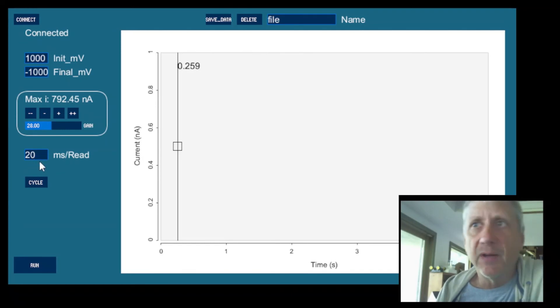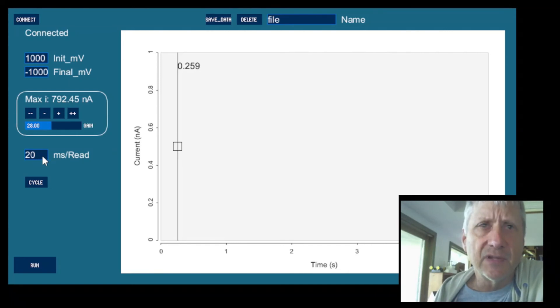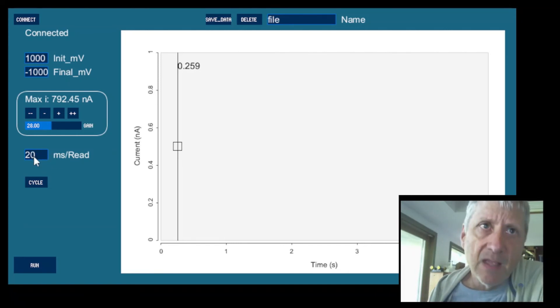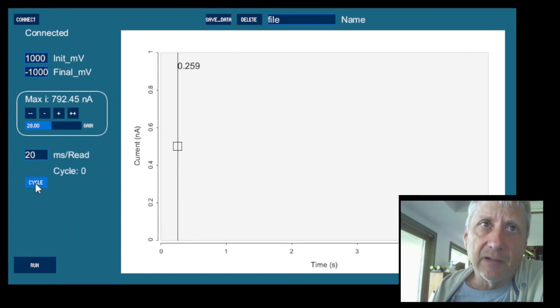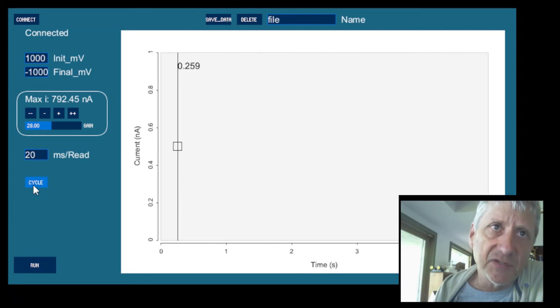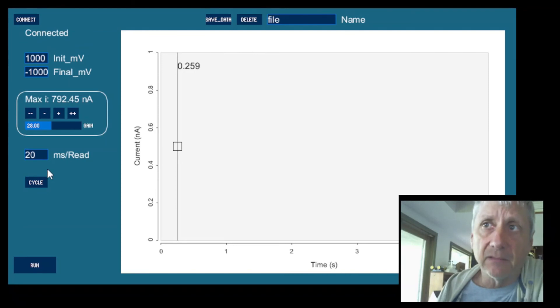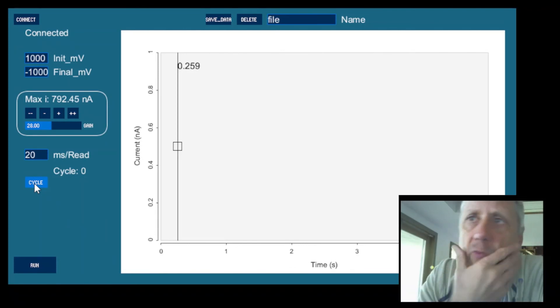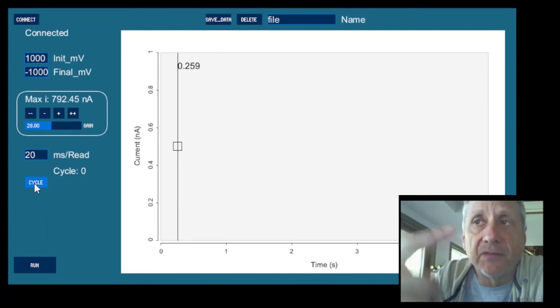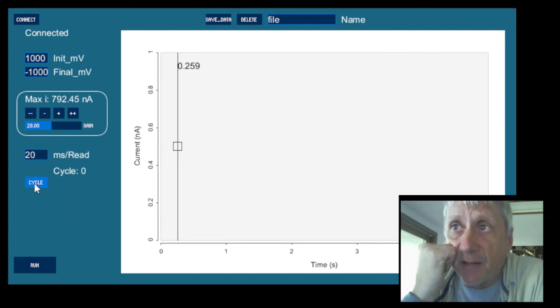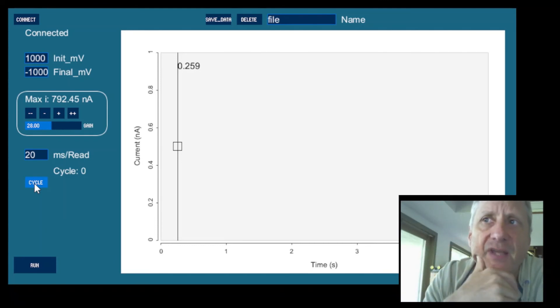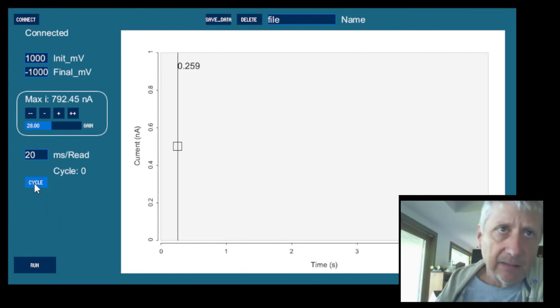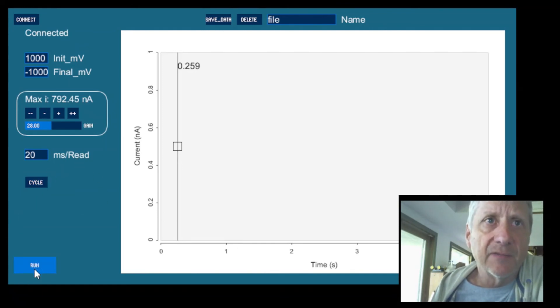So every 20 milliseconds or 50 per second, the deal is we can control how frequently we're sampling. This button down here tells you whether you're going to cycle infinitely or not. The reason I have this cycle button is that if you run the cycle program, it's going to continue until your instrument runs out of battery. So once I get my battery power set up, that will be how I will test the battery. And let's turn that cycle thing off for the time being and we'll hit the run button and see how it does.